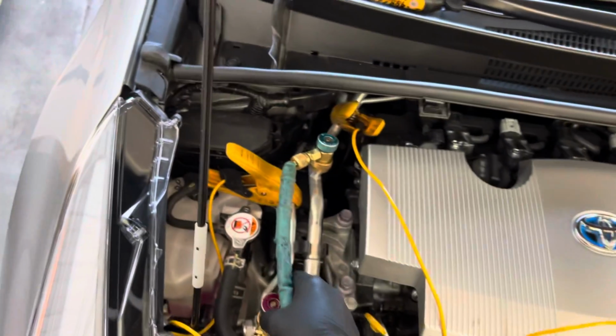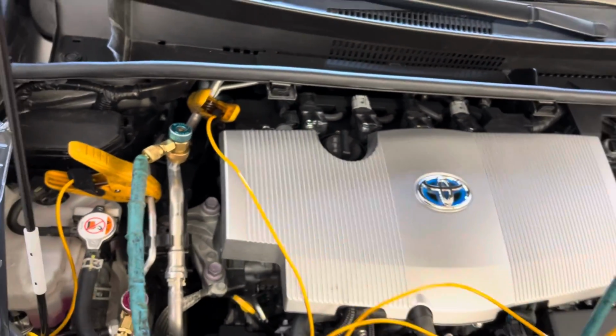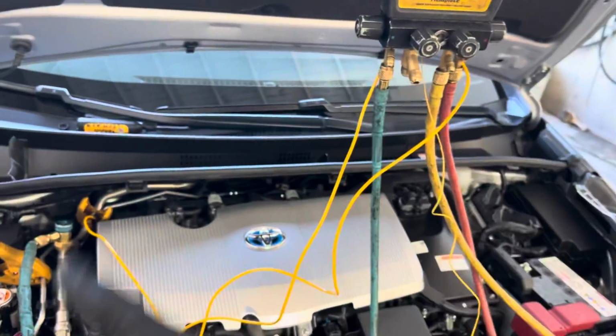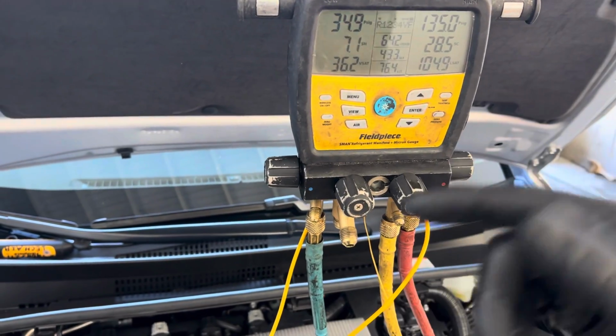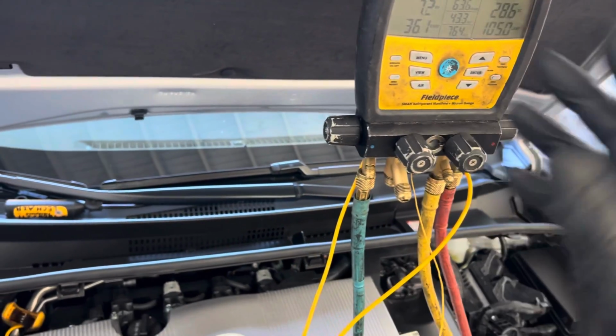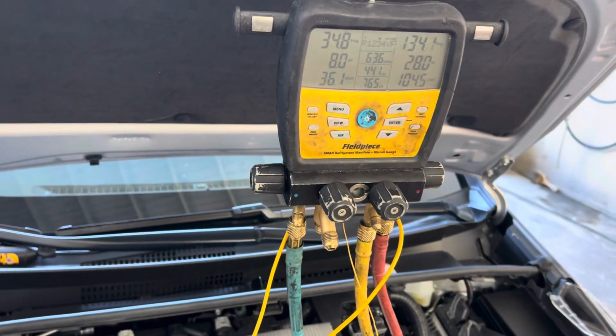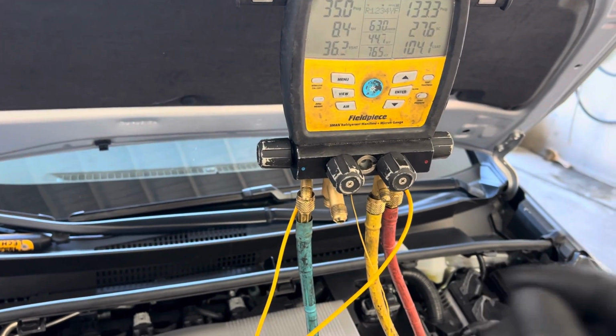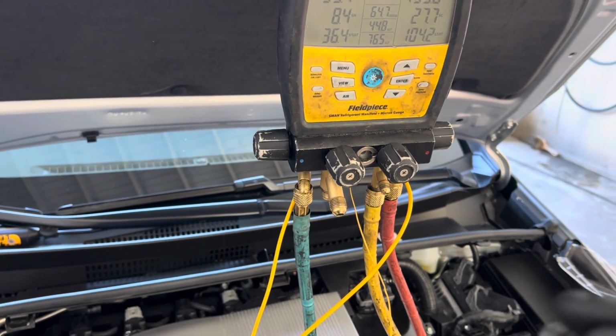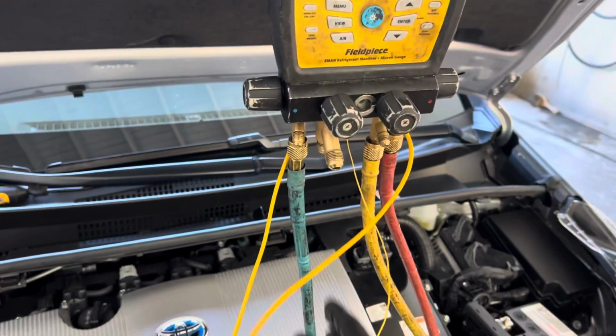The right way is to isolate it off and have a separate micron gauge not connected to any hoses from a refrigerant manifold. I don't always stress that, but I used to stress that a lot before. But I guess it's time for me to make some videos showing comparisons again with hoses and without hoses, what your micron gauge readings are. It's really important to know how to use a micron gauge and know what the readings mean, and know how you can mess yourself up by using gauges with refrigerant hoses.